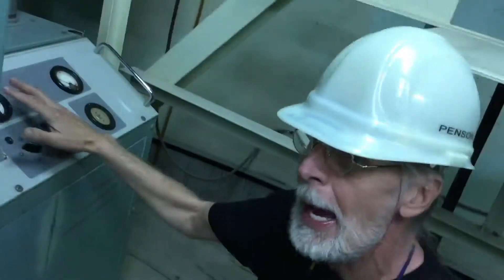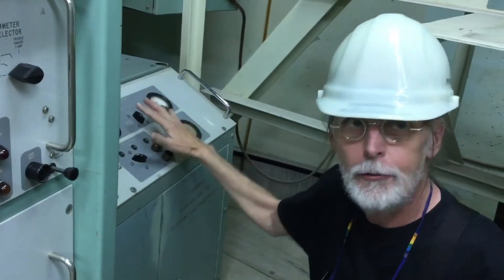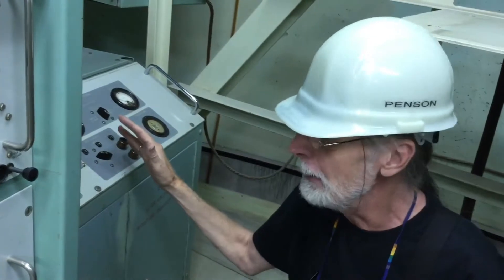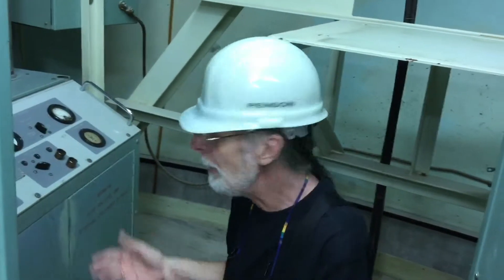That is done with what used to be called a motor generator, and the motor generator is right here. This is long before the days of modern solid-state electronics. This thing is run from the batteries. So if the power goes out, the batteries turn a motor that turns a generator that makes 120 volts alternating current. Today, this whole thing could be reduced to a solid-state package the size of a shoebox. But back then, this is the best you could do.